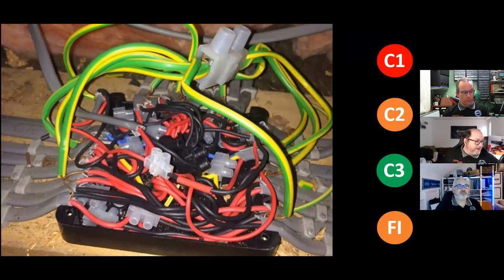I'm pretty much in that ballpark. It's C2 to me as I look at it at first. And then it's a case of, right, is there any other information that takes this to C1? Is it likely that people are going to be walking or crawling past it when they go into the loft space? Is there evidence of scorching or evidence of heating? Is there other things that push it into C1?